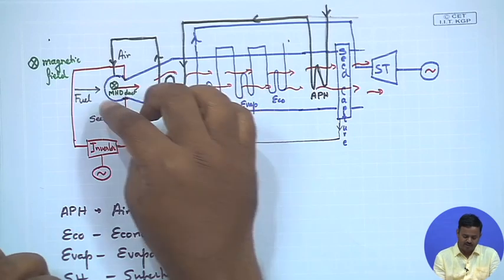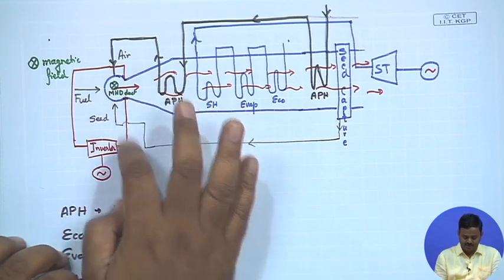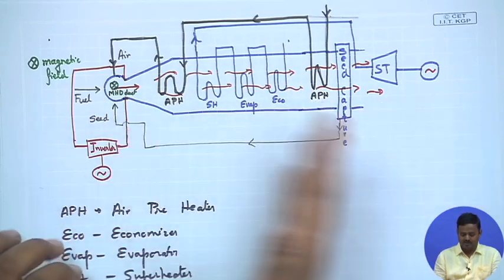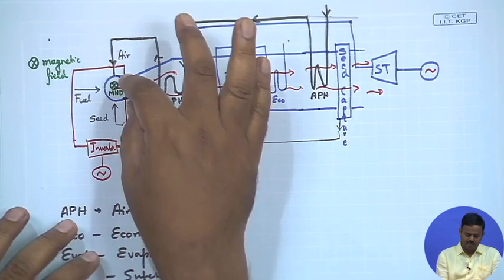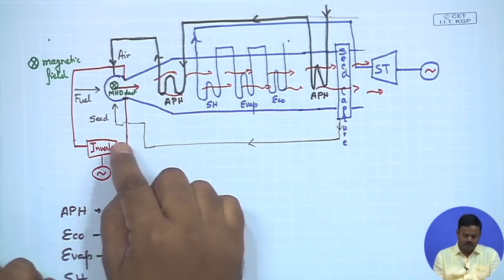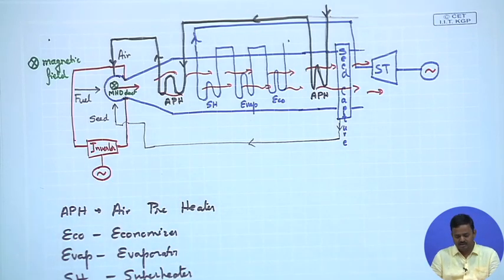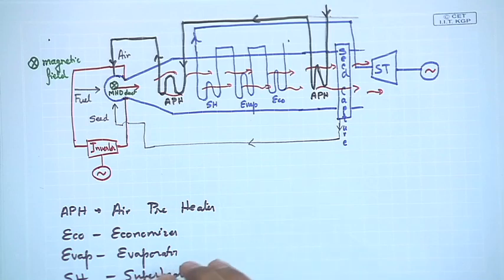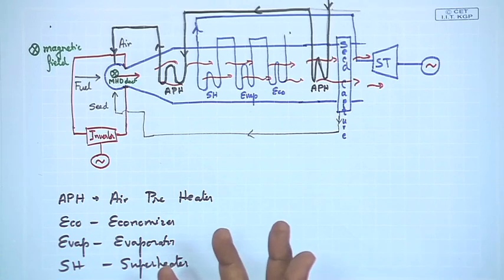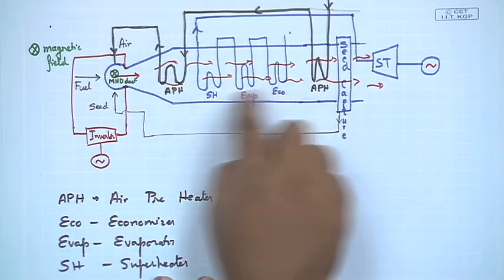To summarize the schematic: we have an MHD duct with combustion gases at very high temperature; a magnetic field is applied perpendicular to the plane; the hot ionized seeded gas moves in the x-direction; the DC voltage is measured across the y-direction; an inverter converts it to AC. Once the gas cools below 2000 K and loses its ionization potential, it is used as a heat source in the boiler and for air preheating.